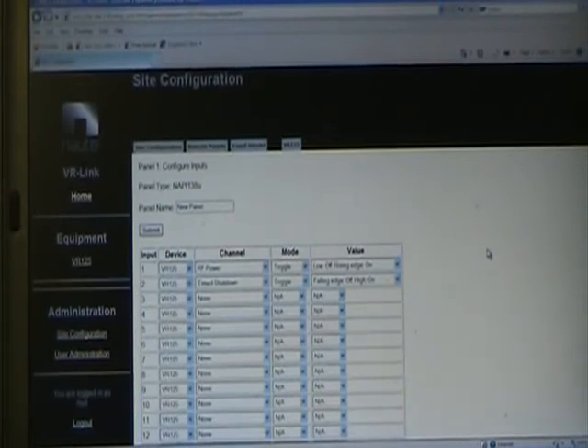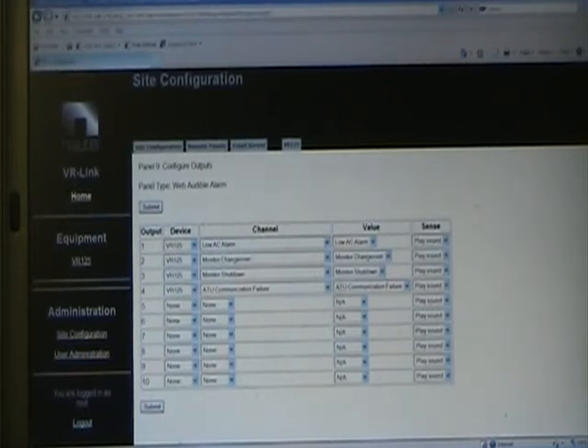The ECMP has three switches and a number of lights that we can change the meaning of. Right now we have RF power, toggle, and timed shutdown as the switched inputs — and I can change them to whatever I want. If we had multiple ECMPs connected, we would see more than one panel listed here — panel one, panel two, and so on. The audible alarm feature, if you have your speakers on and you set an alarm, can trigger a WAV file to play on your computer.